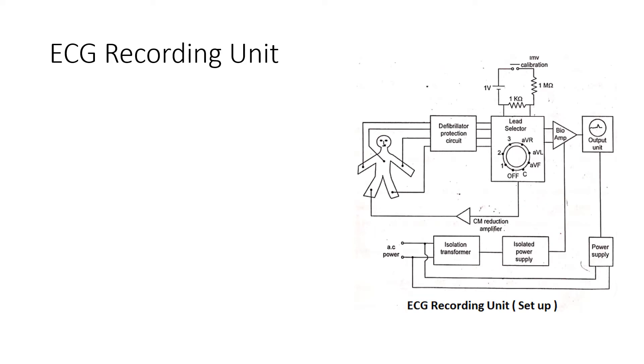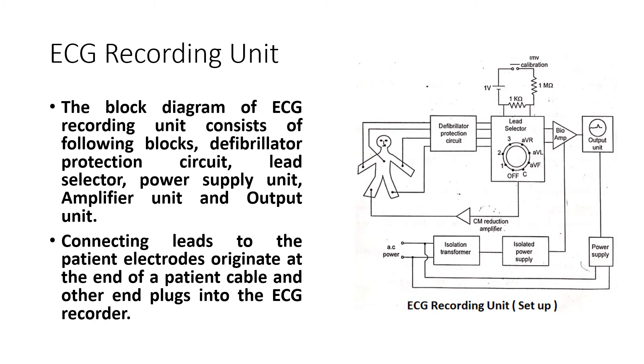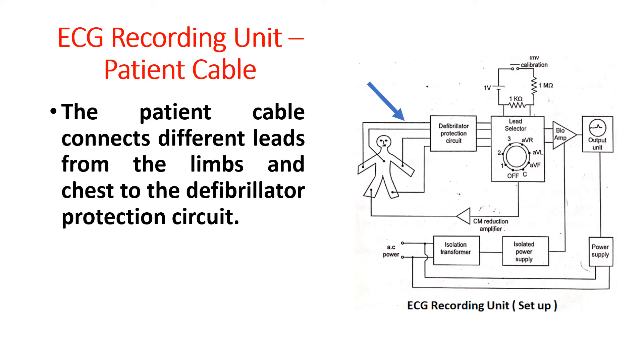ECG recording unit. The block diagram of ECG recording unit consists of the following blocks: the defibrillator protection circuit, lead selector, power supply unit, amplifier unit, and output unit. Connecting leads to the patient — electrodes originate at the end of a patient cable and the other end plugs into the ECG recorder. The patient cable connects different leads from the limbs and chest to the defibrillator protection circuit.